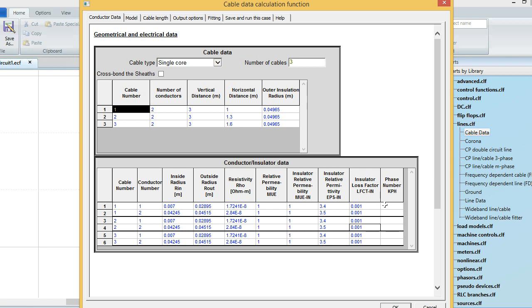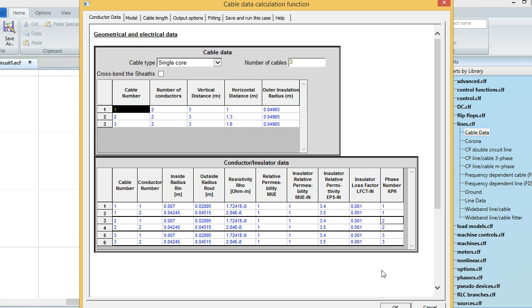What is the phase number? I have three phases numbered 1 to 3, but the two conductors inside the same phase share the same phase number. I can also determine here if the sheath is grounded — a value of 0 means the conductor is grounded. I don't want any conductors grounded, so I'll give each a distinct value.